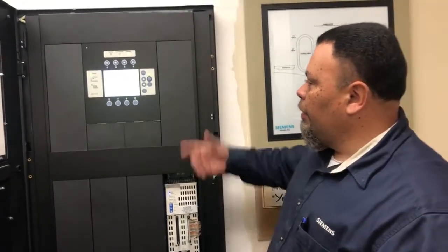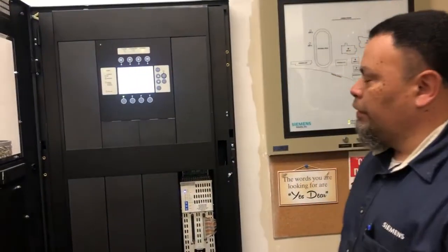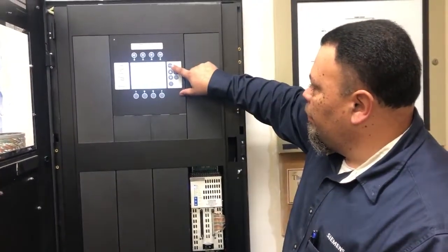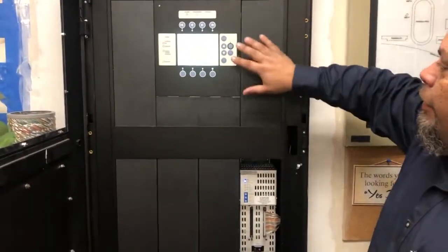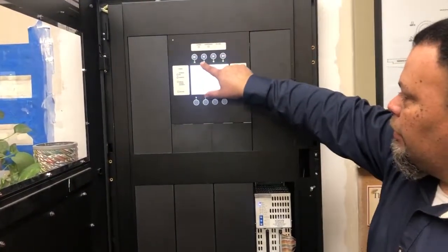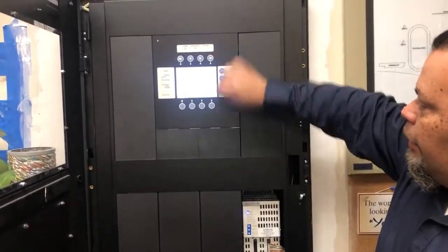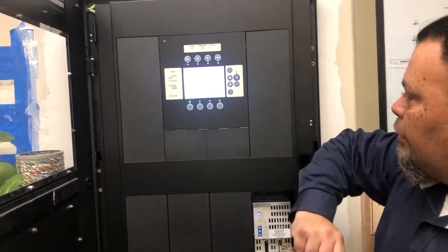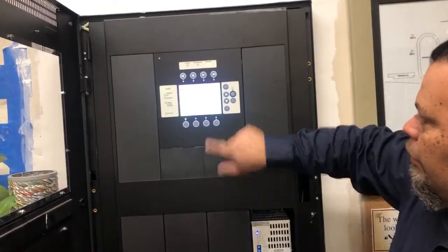If anybody here in maintenance needs to disable certain things for testing purposes, we'll go into your menu button. Normally, this is going to read normal, correct, when there's no troubles? Yes. You'll hit your menu button, and then these lights are illuminated green for these functions that you are now allowed to do. The function keys are your bypasses. So you can bypass your horns and strobes. You would hit that button. It is touchscreen, and then you hit the execute button.